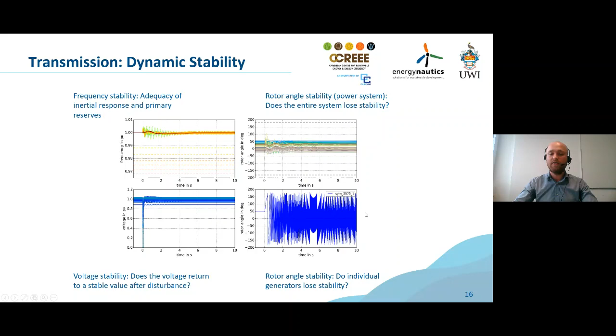You could also look at rotor angle stability, whether generators would lose angle stability, and voltage stability, looking at what would happen during a short circuit on one of your transmission lines. Also, as mentioned before, the capability of low voltage ride-through, LVRT, these simulations can really show you the added benefit from that, because they could potentially show that your system does not return to a stable voltage value after a disturbance, but instead you may end up in a blackout. And lastly, rotor angle stability, as shown in one of the last slides by my previous speaker, needs to remain stable and not go out of that graph.